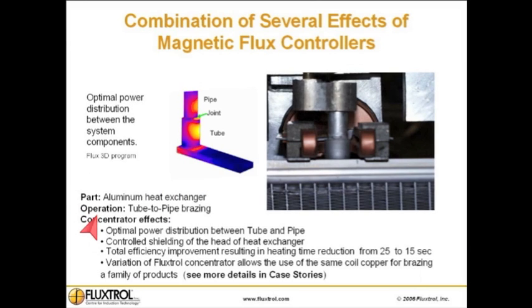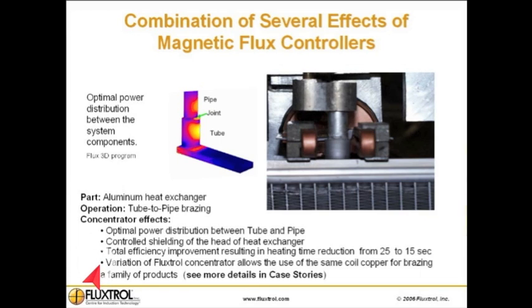Combination of several effects of magnetic flux controllers: in this example, the part is an aluminum heat exchanger and the operation is tube-to-pipe brazing. Concentrator effects include optimal power distribution between tube and pipe, controlled shielding of the head of the heat exchanger, and total efficiency improvement resulting in heating time reduction from 25 to 15 seconds. Variation of flux concentrator allows the use of the same coil copper for brazing a family of products.